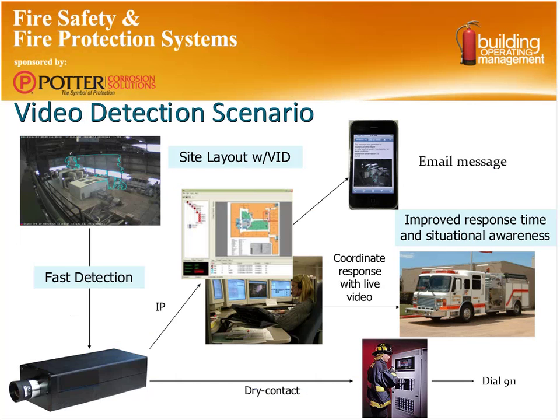And this is a typical fire detection scenario like I was talking about. Fire happens, the camera picks it up, and the information comes up in a graphical format. It can send you an email image of what that camera just saw, the one that went into alarm. If you have a campus-wide facility, you could even get that information to your campus-wide fire department so they can see what it is they're responding to. And through the traditional means, we're also going to get a fire response through the normal dial-out procedure.